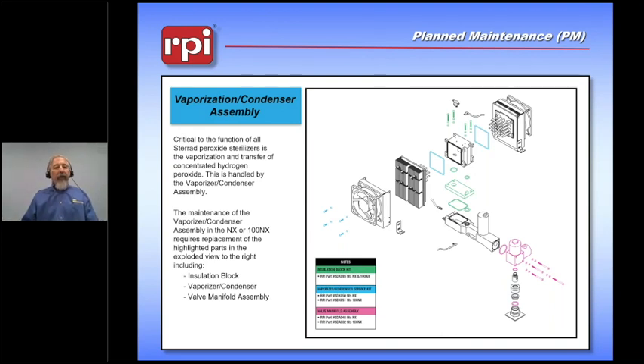Okay, so one of the problems that we have heard about on these machines involves the vaporizer condenser assembly. As we have in this illustration, we've taken the vaporizer condenser and we've blown it apart. Now within this vaporizer condenser assembly, and I'm going to turn my laser pointer on here, the hydrogen peroxide comes in through this tube. It's a swaged fitting. It's delivered into this tray, and then it's vaporized to condense on the rods on the vaporizer condenser assembly.